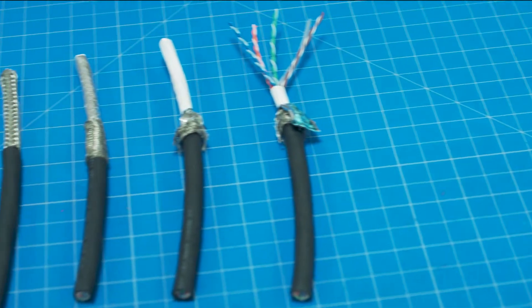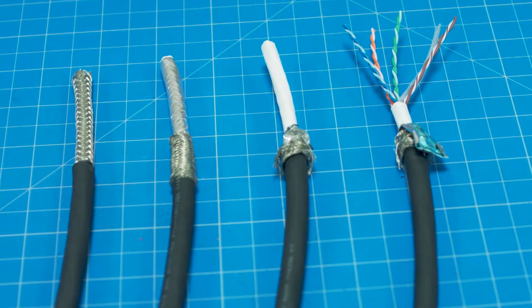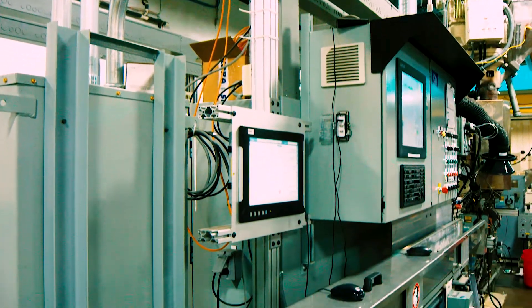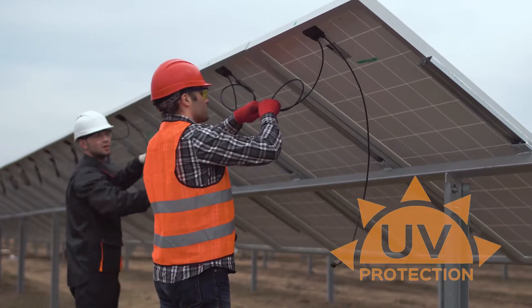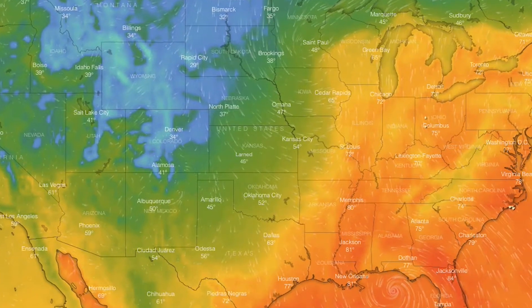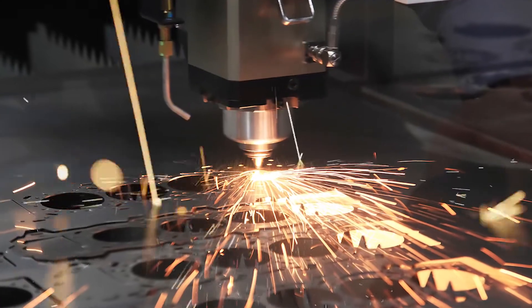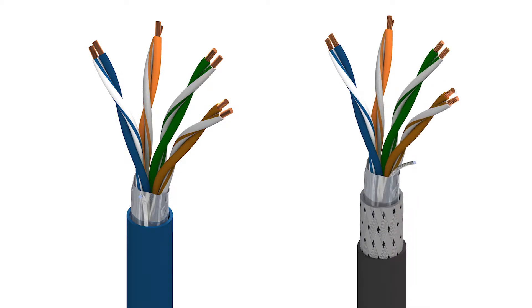Next, let's think about additional levels of protection. Choosing the right cable requires you to consider which jacketing or shielding will enhance your cable performance. Is your installation indoors or outdoors? Do you need to bury the cable underground or will it be exposed to UV rays? What is the typical temperature fluctuation? Are there dust, water, oil, or chemicals present? When you have any of these extreme conditions, consider a more ruggedized cable jacket. If there is a high level of noise at your site, consider a shielded cable. At Belden, you'll find options including braid or foil shielding, or a combination of the two for multiple layers of defense.